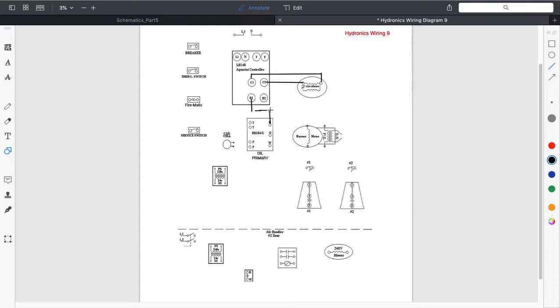The labeling on oil and hydronics, actually on aquastats, is pretty easy to figure out. My W is my neutral. So W is all going to be B2. Okay, and again, I'm going to try to keep this as much together as possible. You know what? I'm going to change my neutral wires to blue. That should help a little bit figure things out. So again, now we're going to extend that W out to my burner motor. Okay. And I am going to come back to black for my O terminal, which is my line supply for my burner motor and transformer.